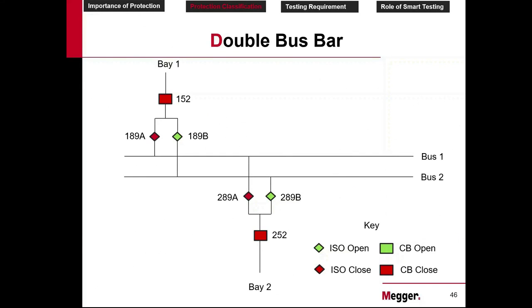So in double bus bar, you have an arrangement like this, that is bus 1, bus 2. You have two isolators connected to bus 1 and bus 2 like this. This one is the isolator, the diamond. And you have breakers 151 and 152 and 252. The first digit stands for the bay number: 152, 252. 52 is the ANSI code for breaker. 89 is the ANSI code for isolator.